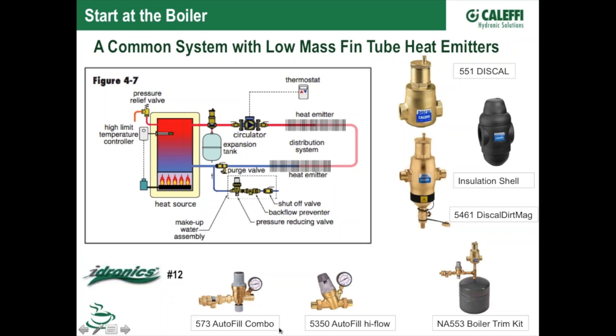Fill valves, what we offer there, what the fill valve does for us in the system is that it puts the initial pressure in the system, what we call the static fill pressure, and that pressure would be decided by how high you have to lift the water up in the building over the level where you're filling it. So if you've got a boiler and you've got 1 or 2 stories above that boiler that you have to lift the water up to, that's what the fill valve is going to do. We've got kits that would include both the expansion tank, the fill valve, and the air purger. That makes it even simpler, so you've got all the solutions in one box.